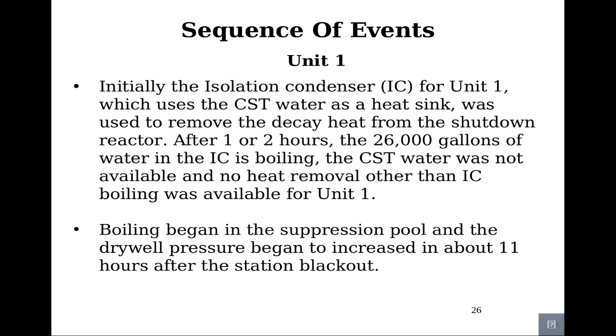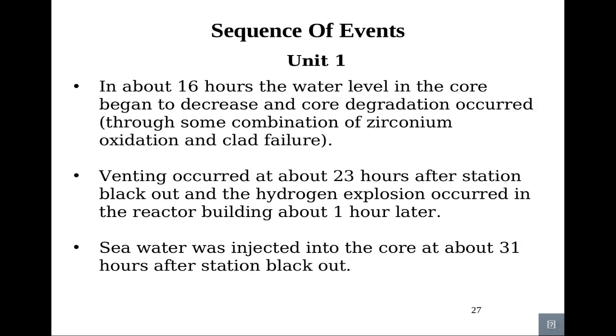After about 2 hours, the 26,000 gallons of water in the isolation condenser is boiling. The CST water is not available, and no heat removal other than IC boiling was available for Unit 1. Boiling began in the suppression pool, and the dry well pressure began to increase about 11 hours after the station blackout. In about 16 hours, the water level in the core began to decrease, and core degradation occurred. Venting occurred at about 23 hours after the station blackout, and a hydrogen explosion occurred in the reactor building about 1 hour after that. Seawater was injected into the core at about 31 hours after station blackout.